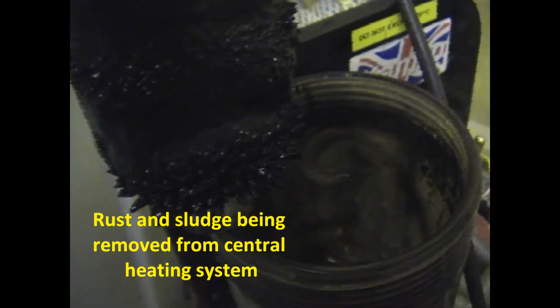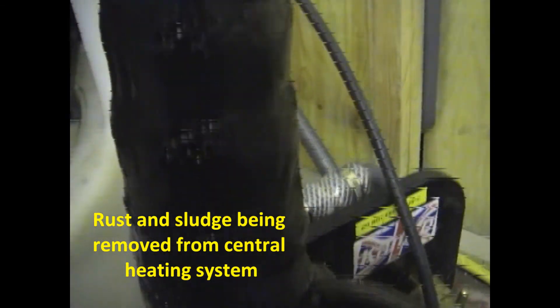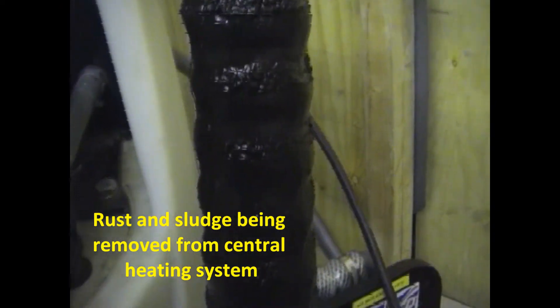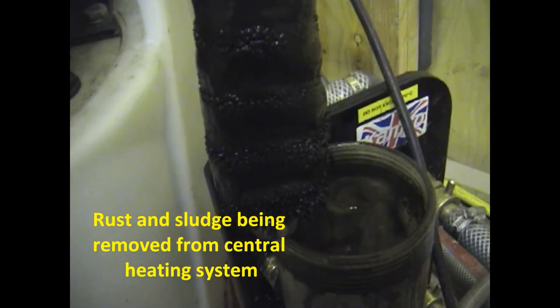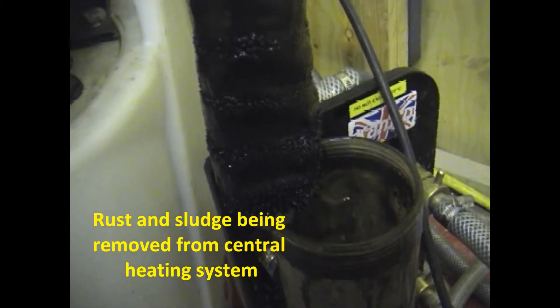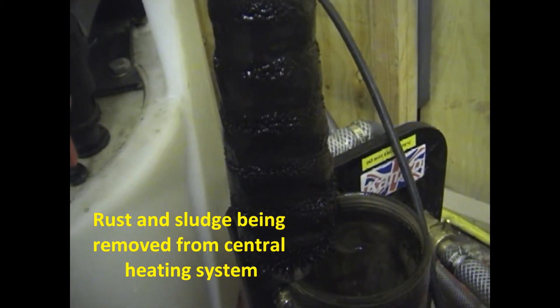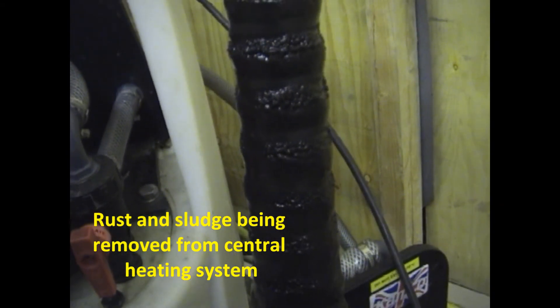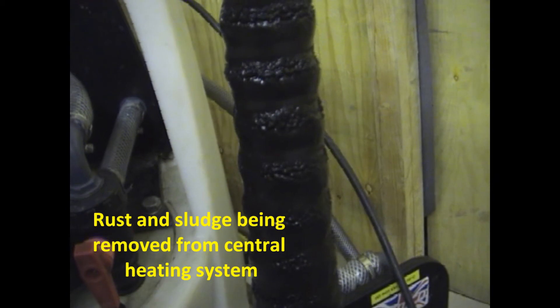There's a lot of metal, magnetite sludge and oxide coming out — some quite fairly big particles of rust as you can see. That's getting all dragged out of the system. That's what destroys pumps, what radiates up metal pipes and your boiler. That's what power flushing is all about — getting all this out of your system.